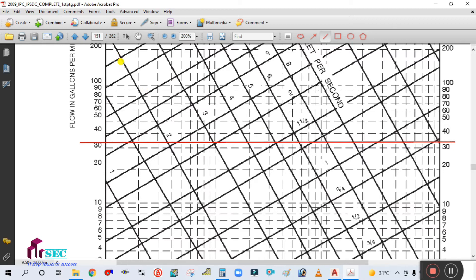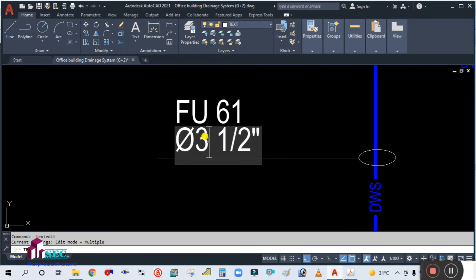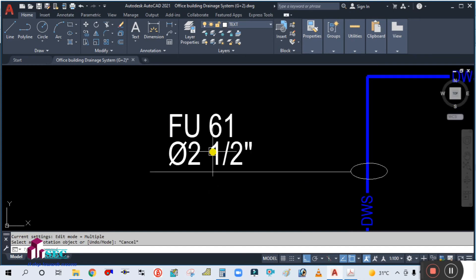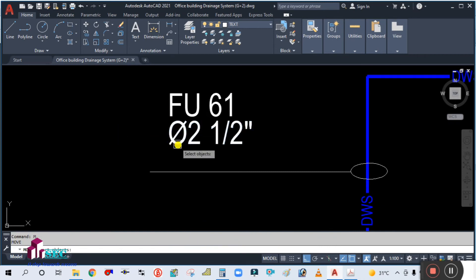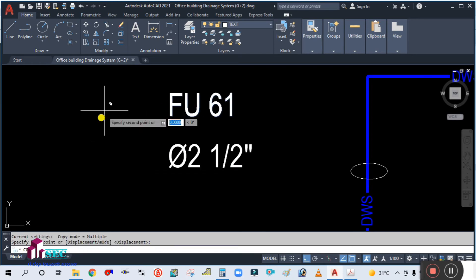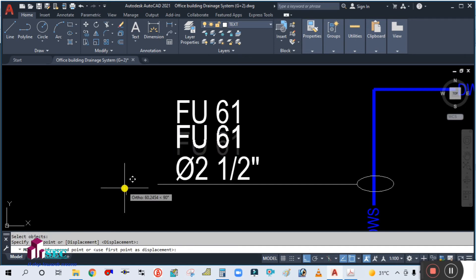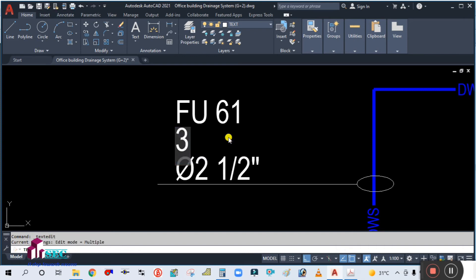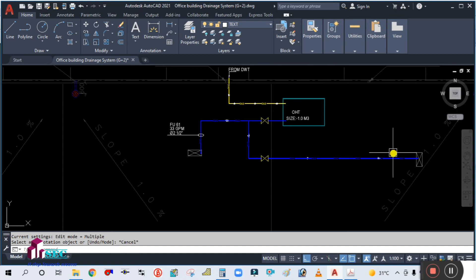Mark 32 GPM on the graph. Velocity is 2 fps, so draw a line at 2 fps and draw the intersection line. The pipe size comes out to two and a half inch — not three inch. So the pipe size is 2.5 inch, fixture unit is 61, and GPM is approximately 32 to 33. Write this in the drawing.